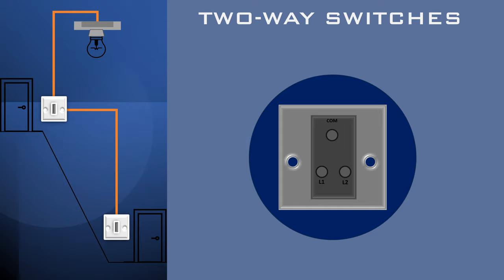Two-way switches allow you to control the light from two different locations. They have three terminals: the common terminal and two traveler terminals, L1 and L2. Each time the switch is operated, L1 and L2 will change over, directing the flow of current.